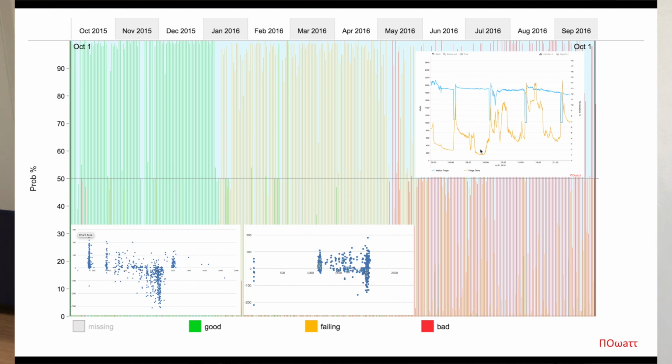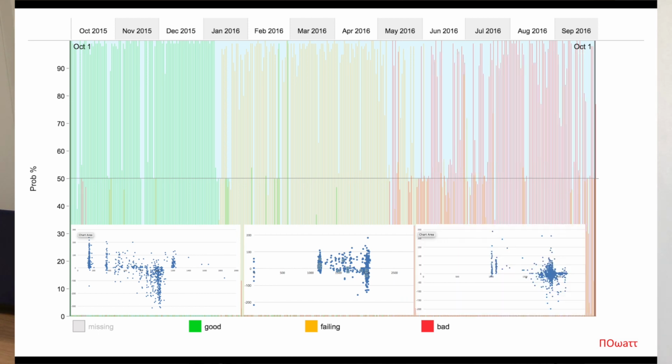And sure enough, after a few months running like that, between January and May, eventually the compressor does give out, and now you can see the compressor's on all the time. Temperature's hardly managed at all. It's all over the place. And so if you take the second order pattern again, it's completely changed again. It's different from this one, and that pattern relates to failed.